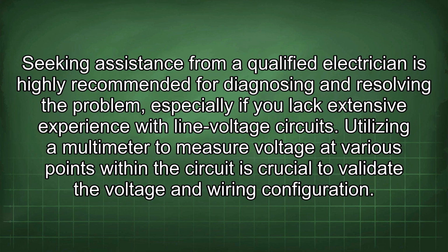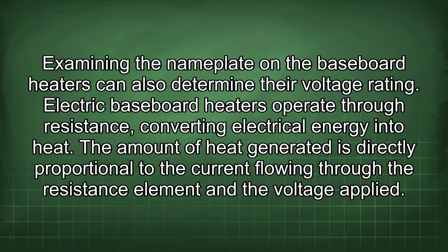Utilizing a multimeter to measure voltage at various points within the circuit is crucial to validate the voltage and wiring configuration. Examining the nameplate on the baseboard heaters can also determine their voltage rating. Electric baseboard heaters operate through resistance, converting electrical energy into heat. The amount of heat generated is directly proportional to the current flowing through the resistance element and the voltage applied.